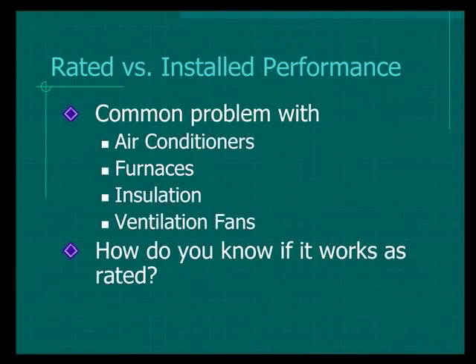It's a big issue in the northern Colorado area. A lot of it has to do with sizing the ductwork for the air conditioner. Typically, ductwork ends up too small, and then the refrigerant charge gets adjusted to make that system even work. So that's not too uncommon. Insulation: John showed you a picture of a knee wall in an attic, that insulation that had no backing on it. That's going to have performance problems. That was probably an R13 rated insulation, and it might be performing at half of that.